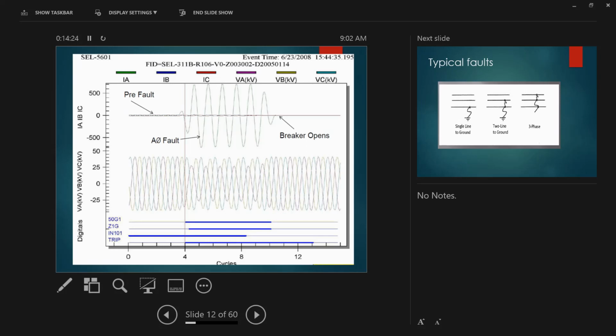For example, when I was involved in design before in the Philippines, some people never understood that there is a difference between the protection CT and the metering CT. Once you install a metering CT in a protection application, it will not work properly, because it will not measure this kind of current, which is thousands of amps, or five or six times the rating. It's only designed to measure accurately at low magnitude. But the protection CT is different. That's why doing the knee point test is very important to determine if it is a protection or a metering CT, because the protection CT is designed to measure accurately at very high magnitudes of current, which the metering CT cannot do. Same with the VT.